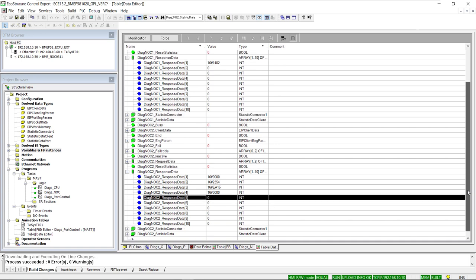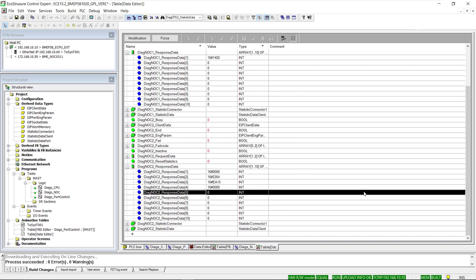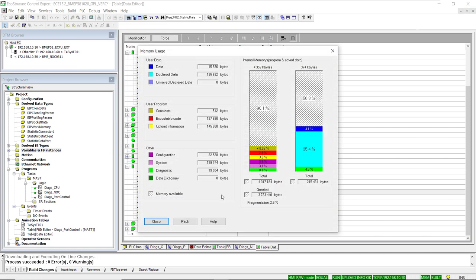Finally, review memory usage, especially for data declaration. In a previous step we had 78.3% of free memory available; now we are left with 56.3%. This is something to consider, especially in programs making extensive use of GPL function blocks — you might want to select a CPU model with more internal memory available.